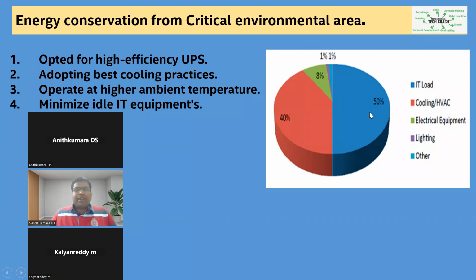When you talk about the 50% IT load, there is not much scope to reduce the power consumption on the IT side, because only when the equipment runs will the production happen and revenue come. Without the equipment's operation, there will not be any production or revenue generation. We cannot switch off the equipment. Equipment should run. Then what are the other options? There is 8% power consumption from the electrical equipment side, and with this equipment there are some losses.